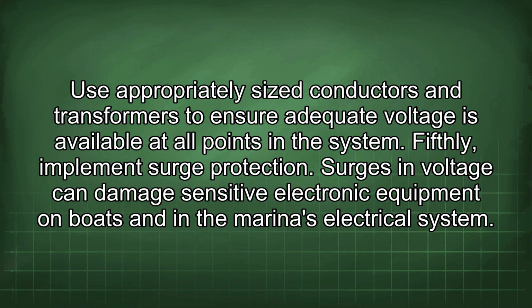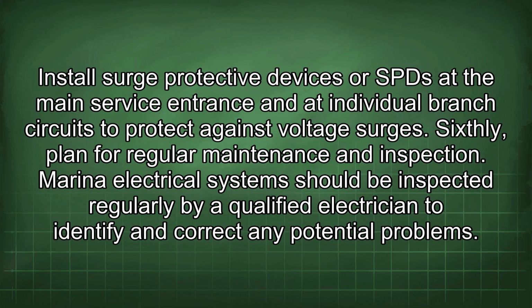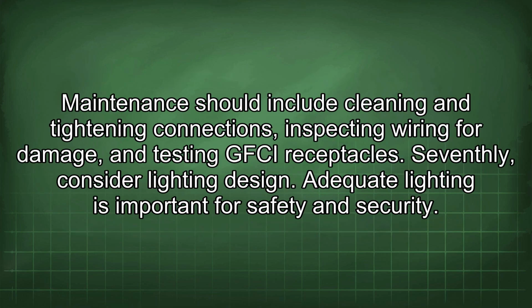Fifthly, implement surge protection. Surges in voltage can damage sensitive electronic equipment on boats and in the marina's electrical system. Install surge protective devices, or SPD, at the main service entrance and at individual branch circuits to protect against voltage surges. Sixthly, plan for regular maintenance and inspection. Marina electrical systems should be inspected regularly by a qualified electrician to identify and correct any potential problems. Maintenance should include cleaning and tightening connections, inspecting wiring for damage, and testing GFCI receptacles.